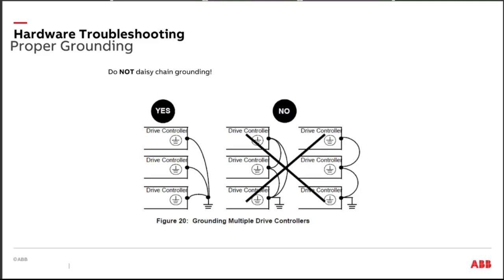And when I went into the job site, the first thing that struck me is they had the drives mounted on 4x8 sheets of 3/4-inch plywood, and they'd used muffler clamps to clamp the plywood onto the handrails of a catwalk. The ground wires were daisy chained from drive to drive, and then they had cut a spot on the handrail and had grounded on the handrail of the catwalk, and it was a mess. It was just a mess. There's not a whole lot you can do with that. You need to have a good ground plane.